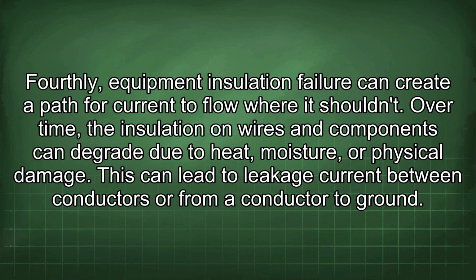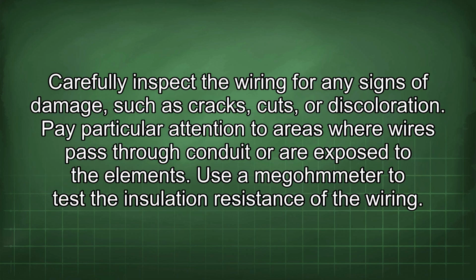Fourthly, equipment insulation failure can create a path for current to flow where it shouldn't. Over time, the insulation on wires and components can degrade due to heat, moisture, or physical damage. This can lead to leakage current between conductors or from a conductor to ground. Carefully inspect the wiring for any signs of damage, such as cracks, cuts, or discoloration.